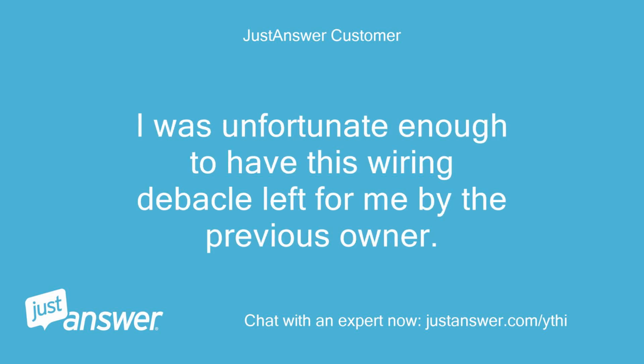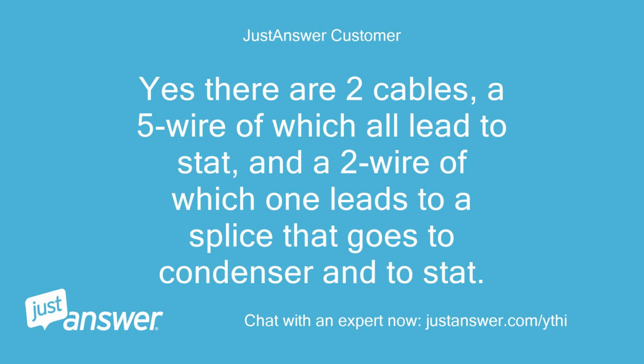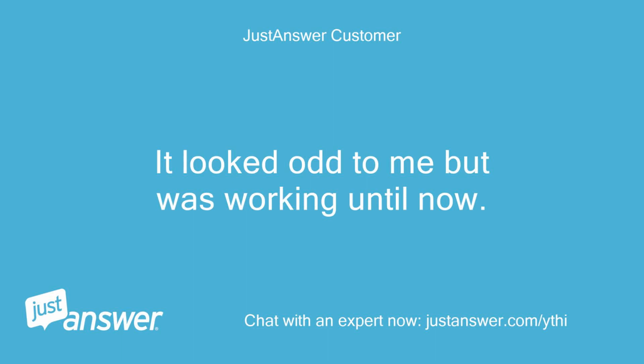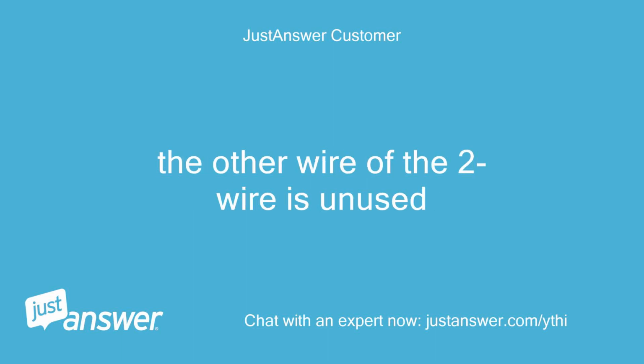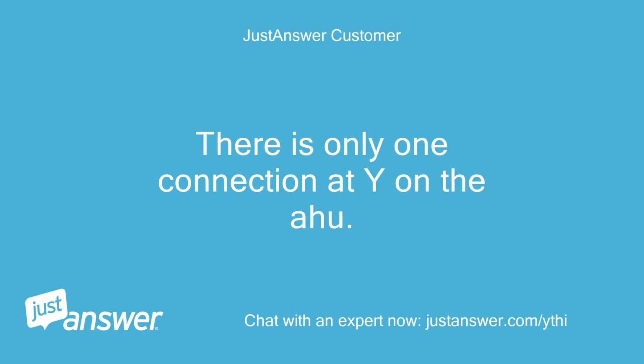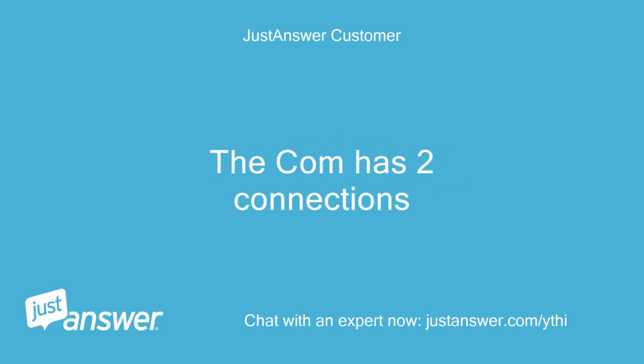I was unfortunate enough to have this wiring debacle left for me by the previous owner. Yes, there are 2 cables, a 5-wire of which all lead to stat, and a 2-wire of which one leads to a splice that goes to condenser and to stat. It looked odd to me but was working until now. The other wire of the 2-wire is unused. There is only one connection at Y on the AHU. The COM has 2 connections.